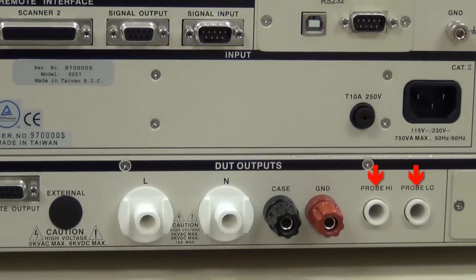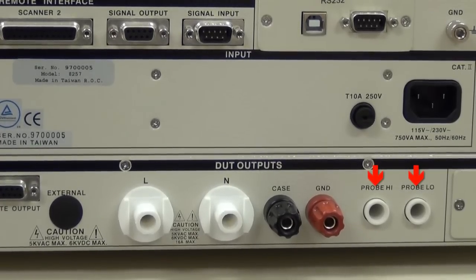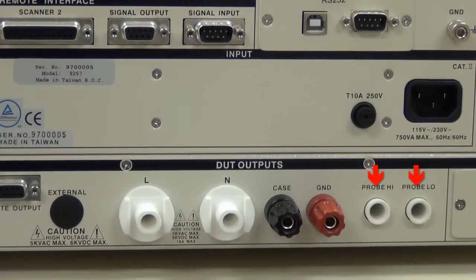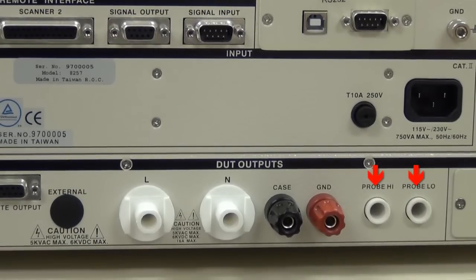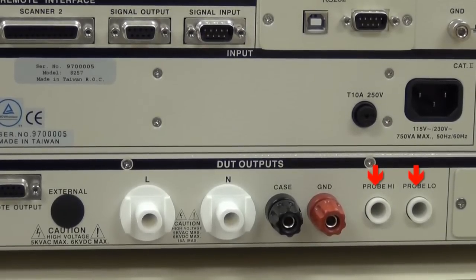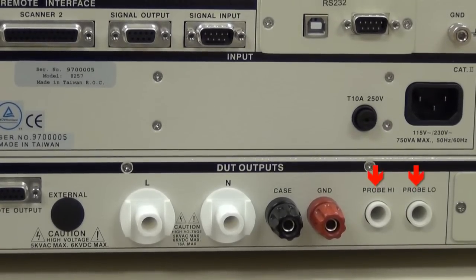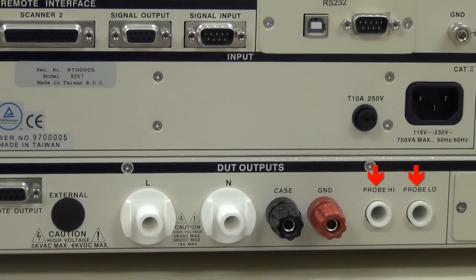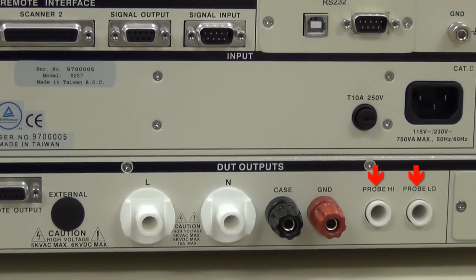The probe high and probe low connectors are used to attach the probe high and probe low test leads to the DUT. When used with the appropriate test leads, these terminals connect one side of the measuring device to the DUT during enclosure, touch, or patient leakage testing. These terminals will be enabled during a line leakage test whenever probe high to line or probe high to probe low has been selected. When a functional run test or line leakage test is not being performed, these terminals are isolated from the line leakage or functional run test circuits.